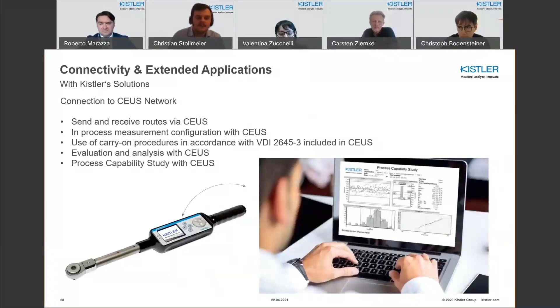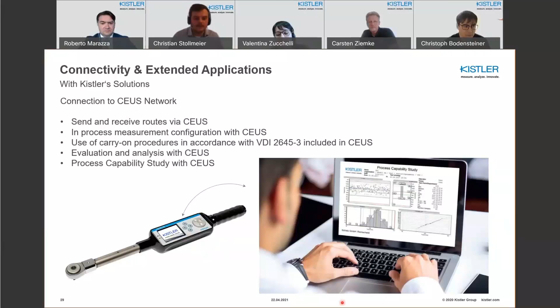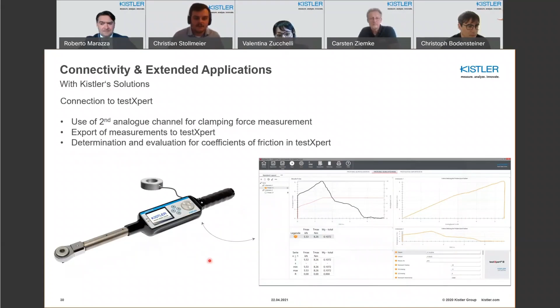We have the possibility to work along routes on the assembly line. The route means we have a task of measurements that we need to do, which will be parameterized by CEUS, done with the inspector wrench or the Inspect Pro, and afterwards transferred back to CEUS for evaluation. And also with the inspector wrench, we have the possibility to connect a small load cell in order to do a coefficient of friction measurement.